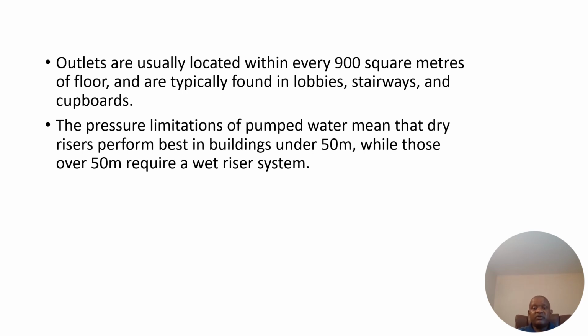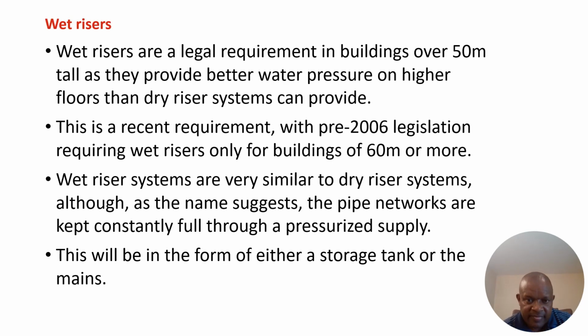Outlets are usually located within every 900 square meters of floor and are typically found in lobbies, staircases, and cupboards. The pressure limitations of pumped water mean that dry risers perform best in buildings under 50 meters, while those over 50 meters require a wet riser system.